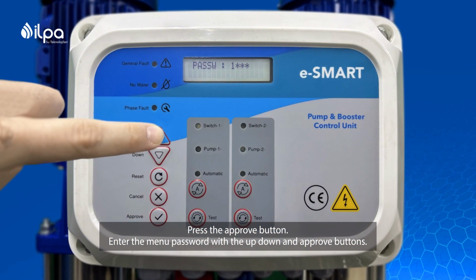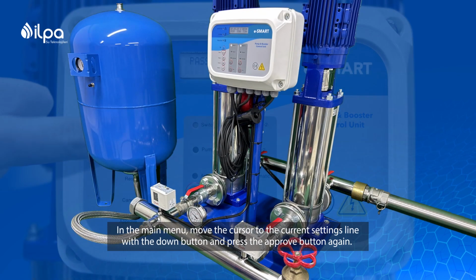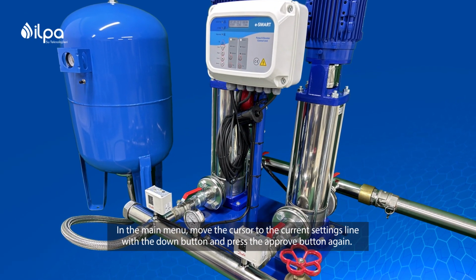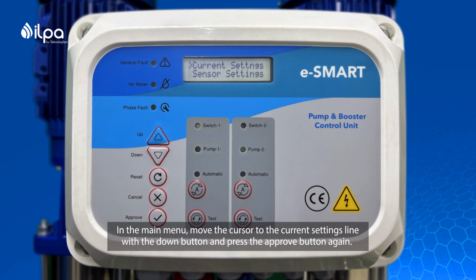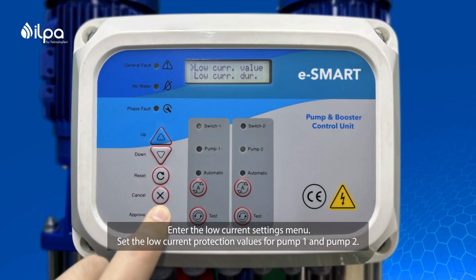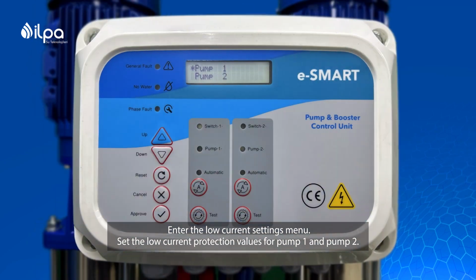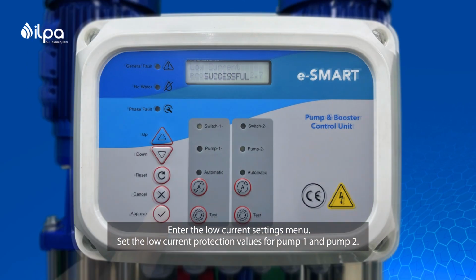Enter the menu password with the Up, Down, and Approve buttons. In the main menu, move the cursor to the current settings line with the Down button and press the Approve button again. Enter the Low Current Settings menu. Set the low current protection values for Pump 1 and Pump 2.